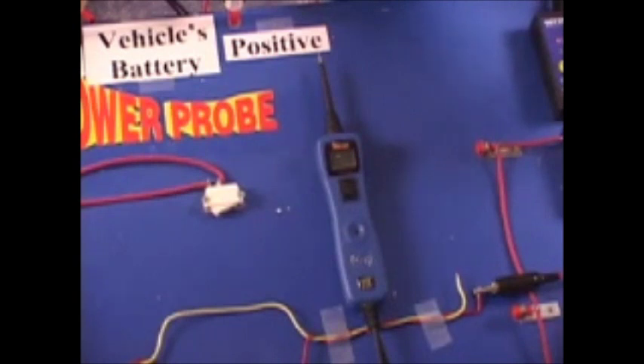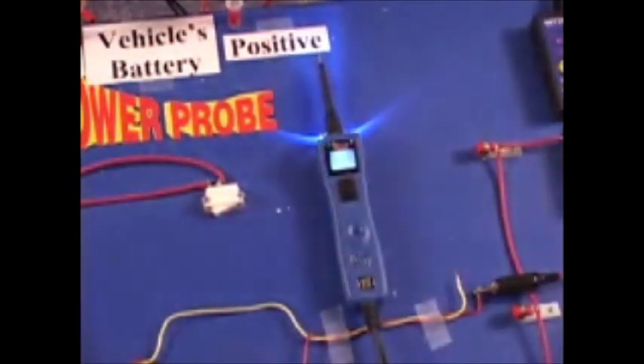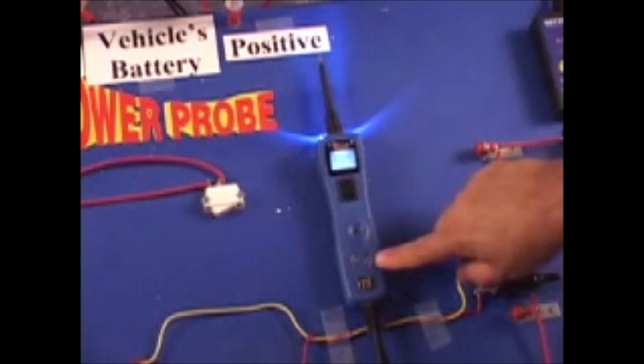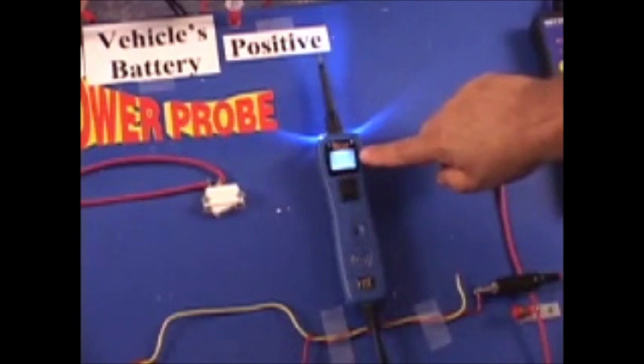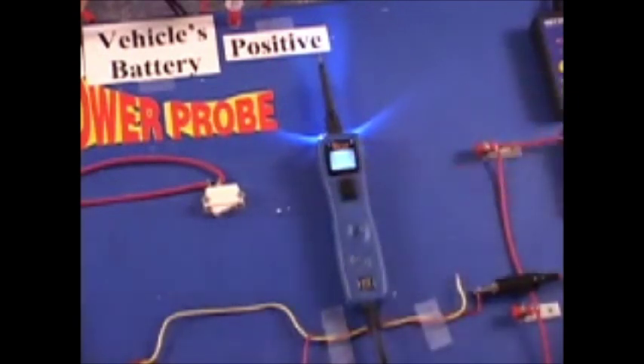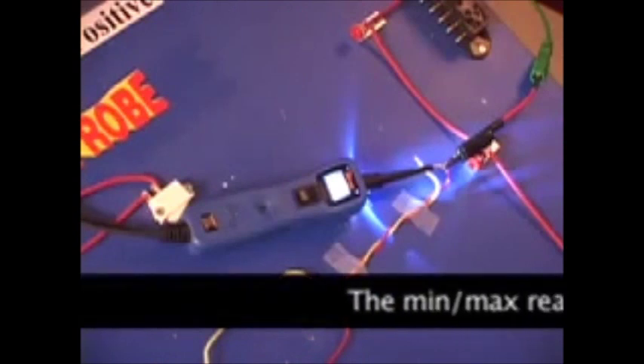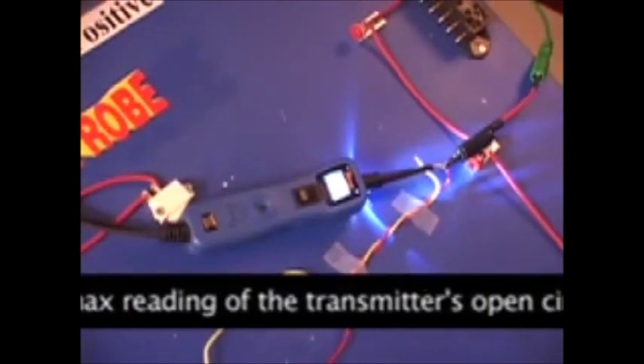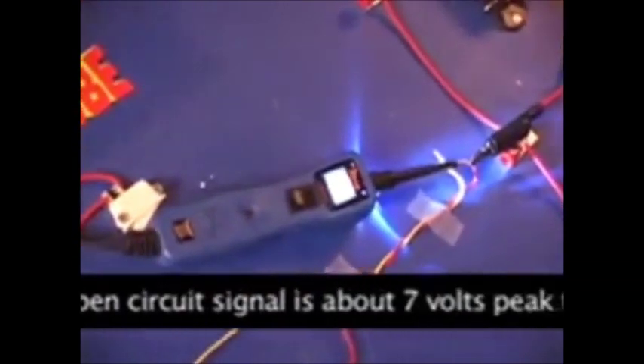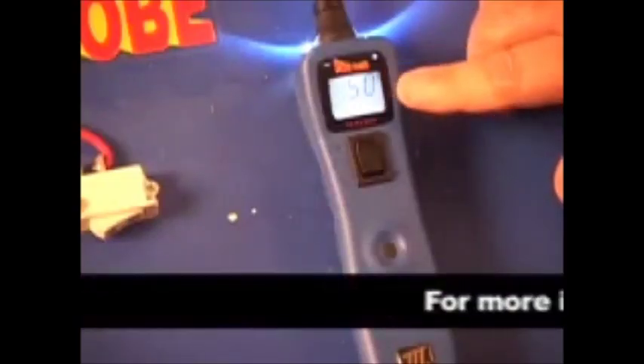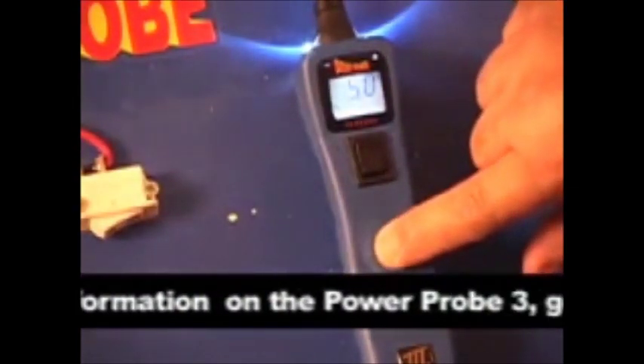The Power Probe 3 will detect your open circuit signal because it has an invaluable feature built into its Power Probe mode. It has the ability to pick up circuit noise or signals, and you can hear them through the speaker. At the same time, it'll give you a peak-to-peak reading on the display. Some may know this peak-to-peak term as min-max. Just for your information, the min-max reading of the transmitter's open circuit signal is about 7.2 or 7.3 volts peak-to-peak. So therefore, the Power Probe should have its voltage level threshold set at 5 volts.